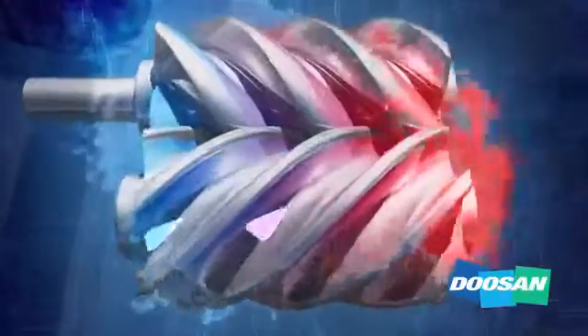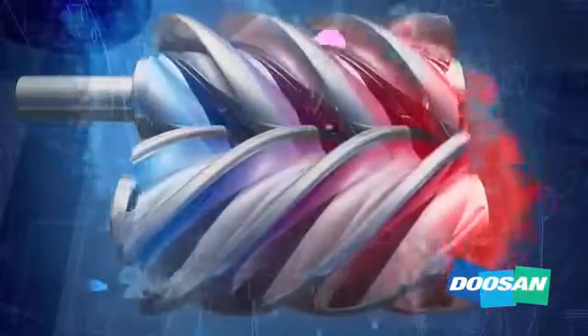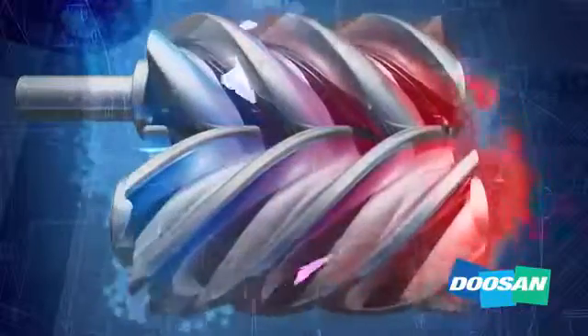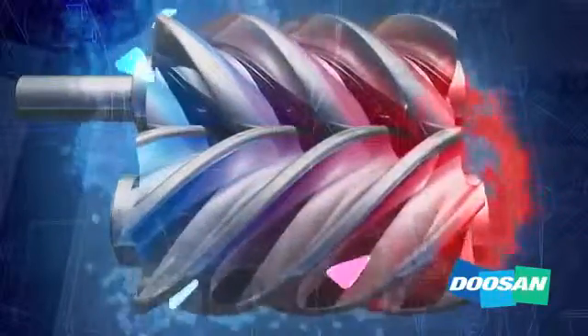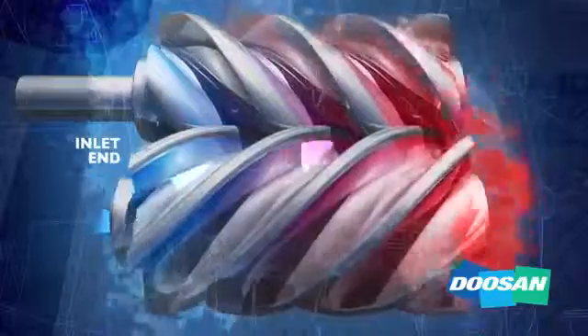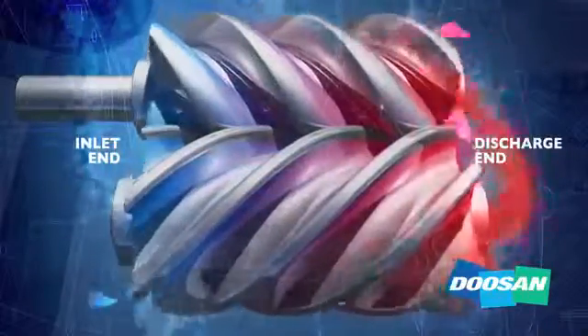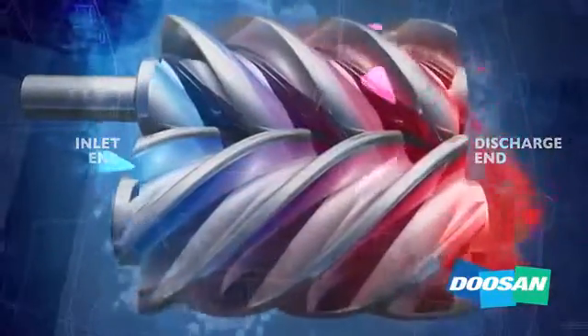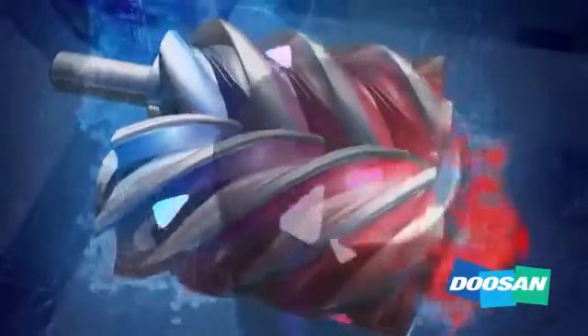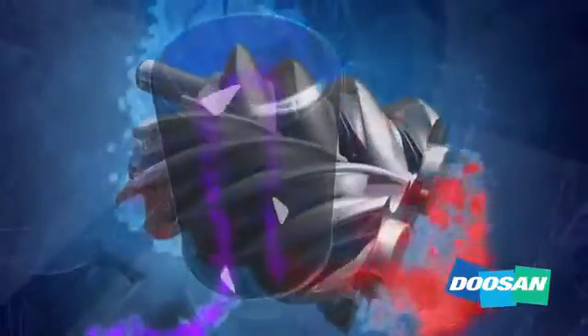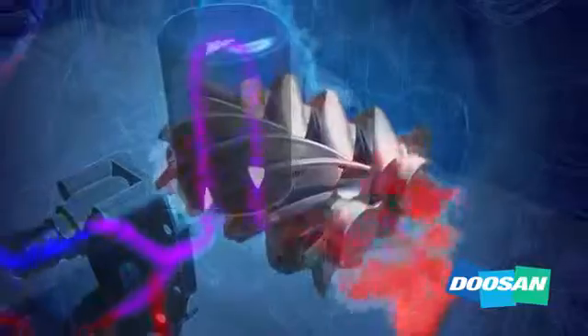As air travels along the helical rotor flutes, the space storing the air gets progressively smaller. Since the air cavity between the rotors is larger at the inlet end and smaller at the discharge end, air becomes compressed, creating significant heat. During the process, oil is injected into the rotors and serves three critical purposes.